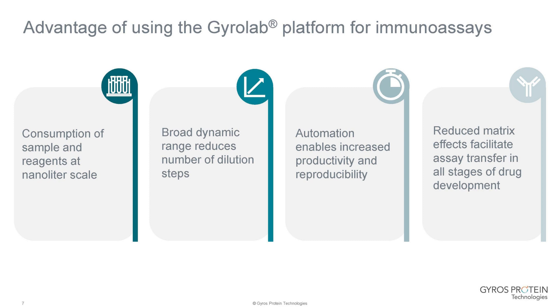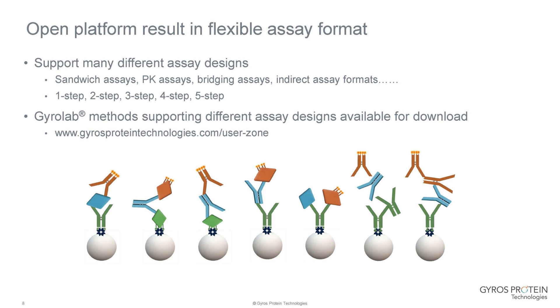An assay takes approximately one hour to perform. The platform is an open platform, offering a flexible approach. It can support many different assay designs: sandwich assay, PK assays, bridging assays, indirect assay formats. We can have one step, two step, three step, four step, and five step formats, for example. All these methods can be downloaded from our user zone, so end users have a lot of flexibility in how they use the platform.